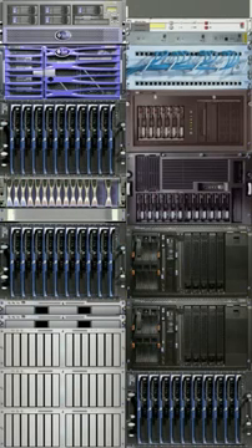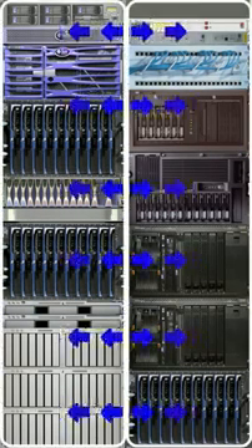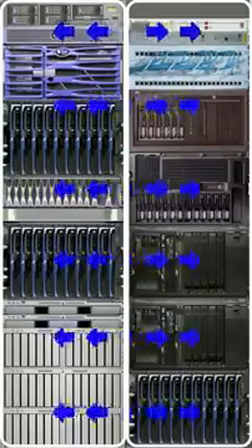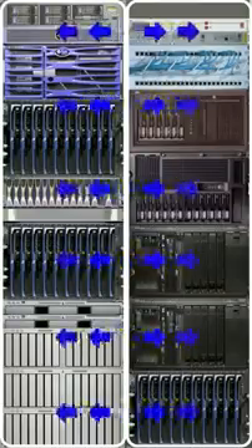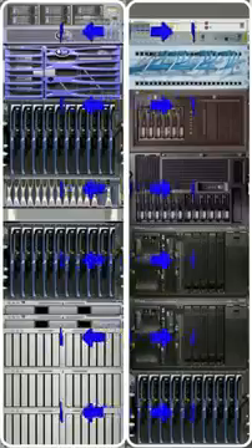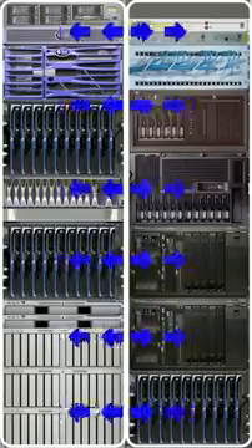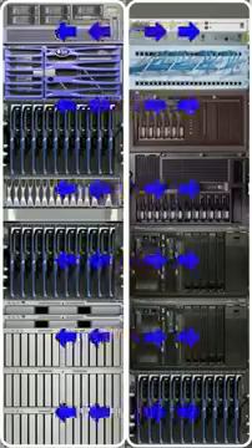Because of the large cooling capacity of the LCP Plus, it can be shared across a number of enclosures, effectively providing 2 enclosures with up to 15 kilowatts per rack. This gives you a greater flexibility to use the LCP Plus wherever and whenever you need to.